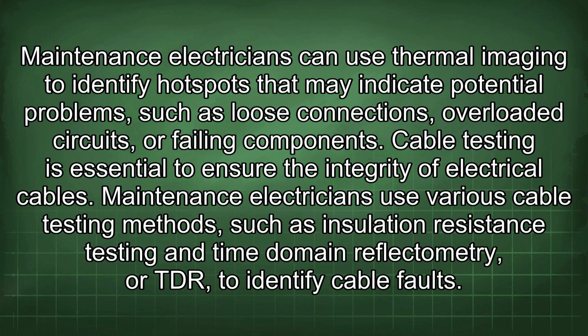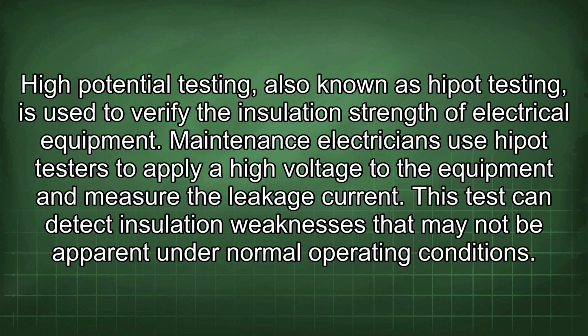High potential testing, also known as HIPOT testing, is used to verify the insulation strength of electrical equipment. Maintenance electricians use HIPOT testers to apply a high voltage to the equipment and measure the leakage current. This test can detect insulation weaknesses that may not be apparent under normal operating conditions.